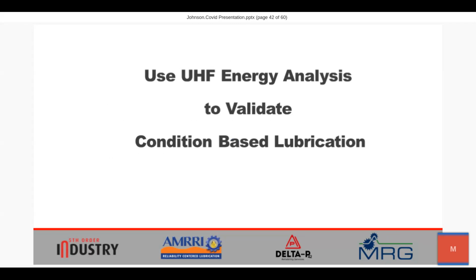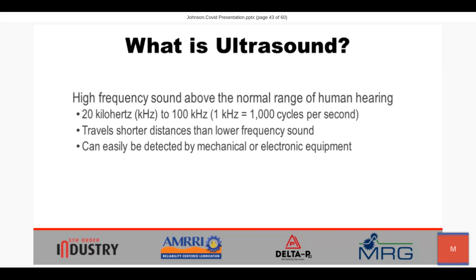It is very, very useful to validate our lubrication practices using ultra-high frequency energy analysis, particularly for electric motors and any other bearings that are grease lubricated and operating in a steady state. This ultrasound is a very high frequency signal, well above human range, in the 20 kilohertz to 100 kilohertz range. It's difficult to identify because it's a very low sound wave that dissipates very quickly as it is produced, and it can be easily detected by mechanical and electronic equipment.